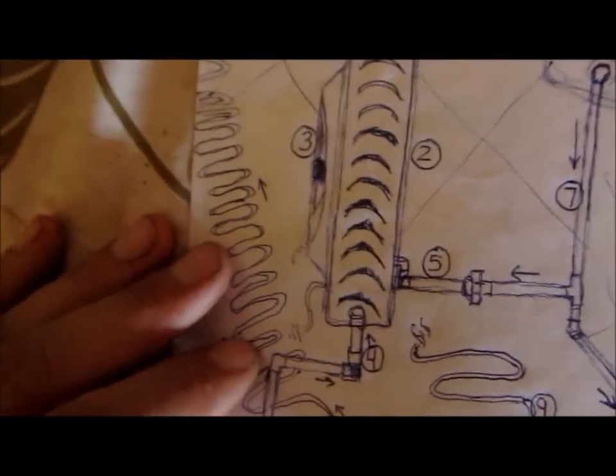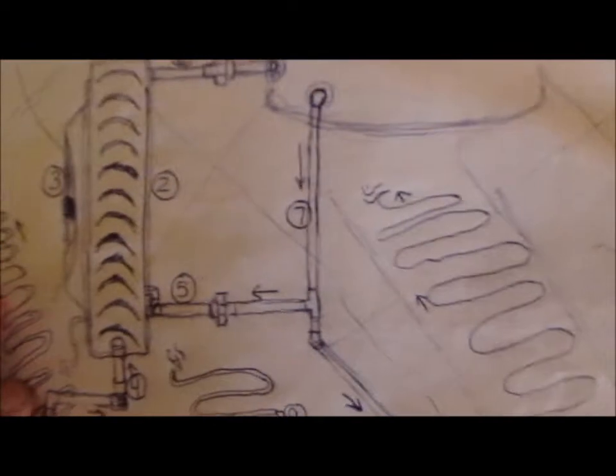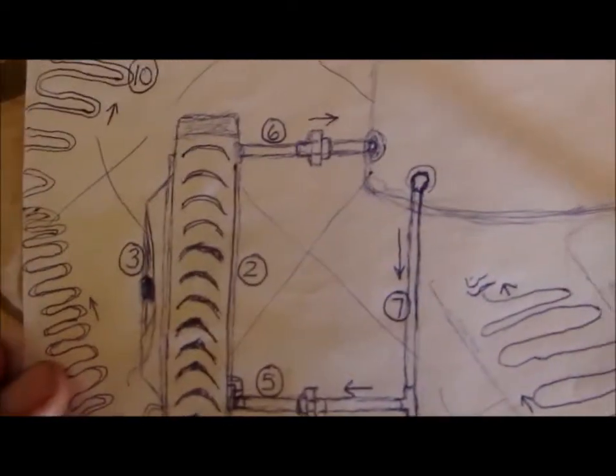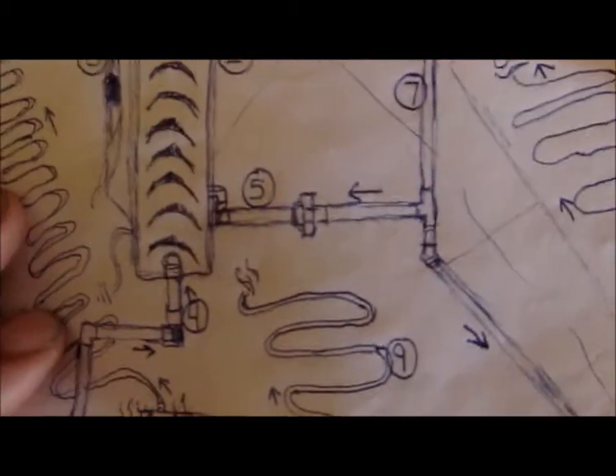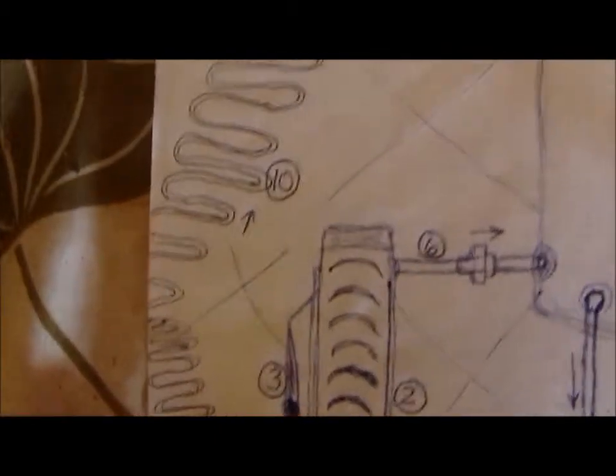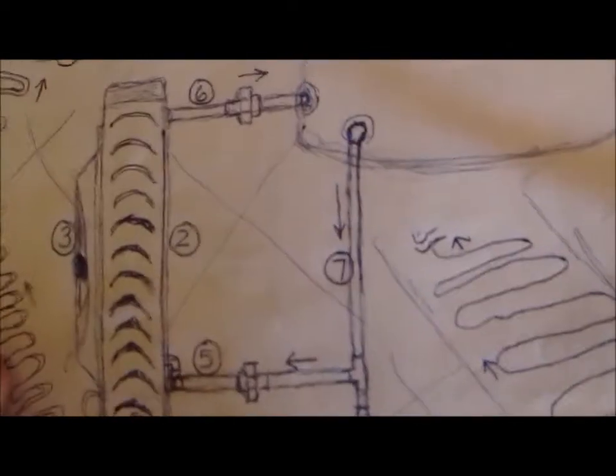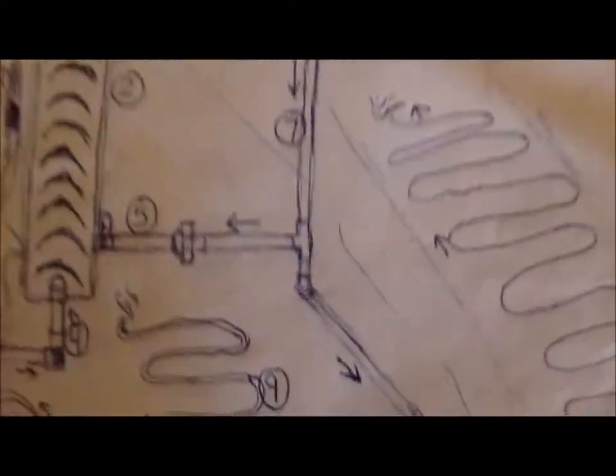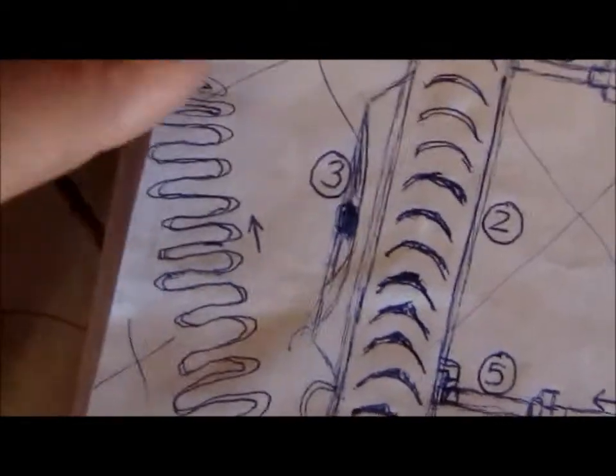The cold water will fall out of this tank into that passively, no pumps, just because cold water is heavier, hot water is lighter, as it expands. It'll drop into here, and as it gets heated by that air, it'll rise back into the tank, and then the loops come down here, drop out of the tank. So when it's sitting here just static, this is what it's doing: it's circulating itself. The cold water is dropping down here, and as it gets heated, it gets sucked up, and it'll be cold down here, so it'll cool your ceiling surface.